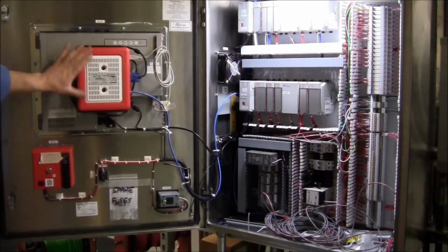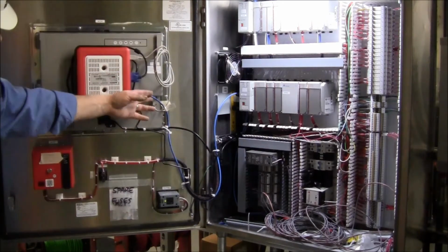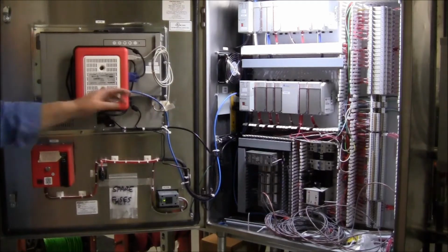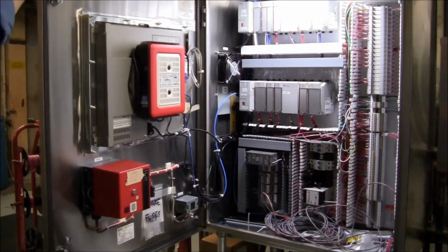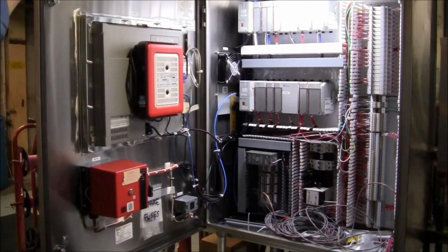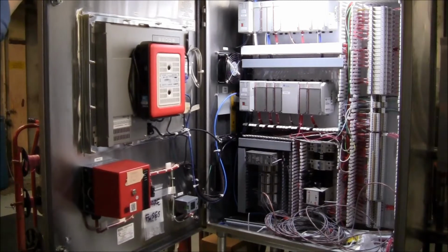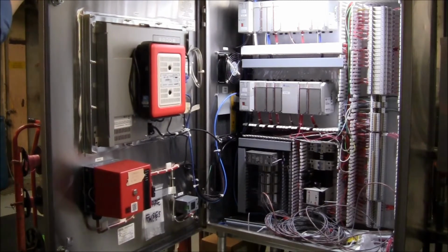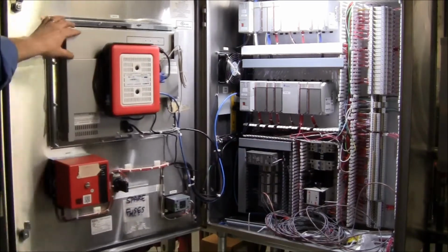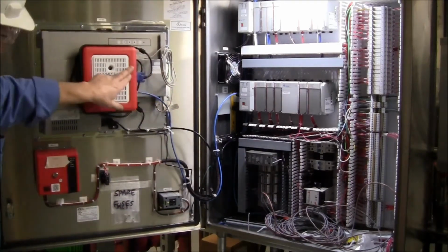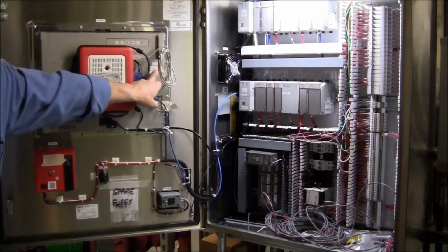So this Arista hooks up to the Land O'Lakes network via Ethernet, and the Arista has software on it called Thin Manager. And Thin Manager is a software application owned by Rockwell Automation or Allen Bradley. We'll talk a bit more about that. And Thin Manager works on a client-server basis where the Thin Manager has an IP address, and each Arista's IP address is on a sticker at each panel.